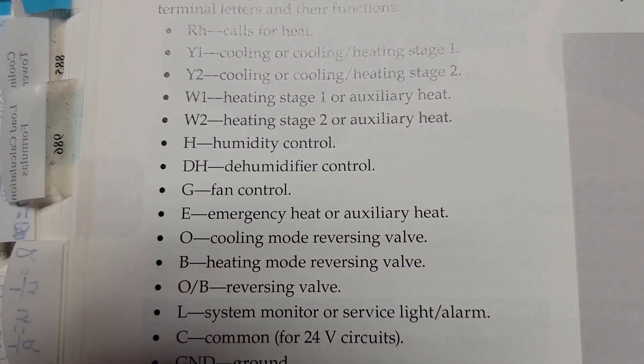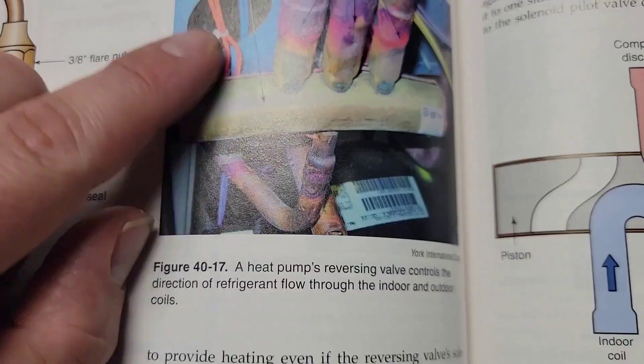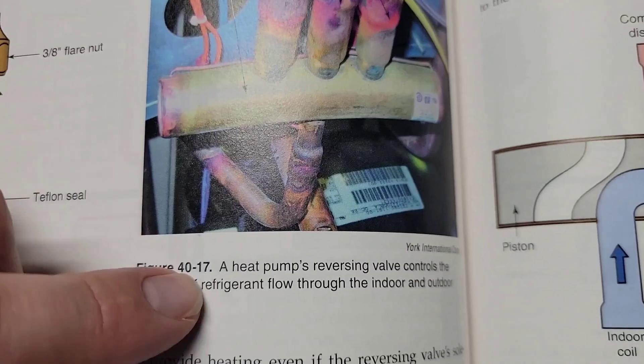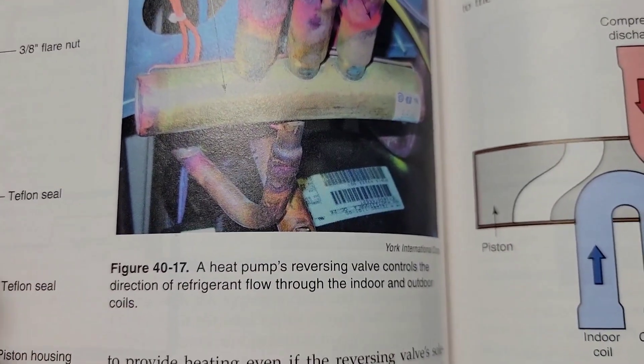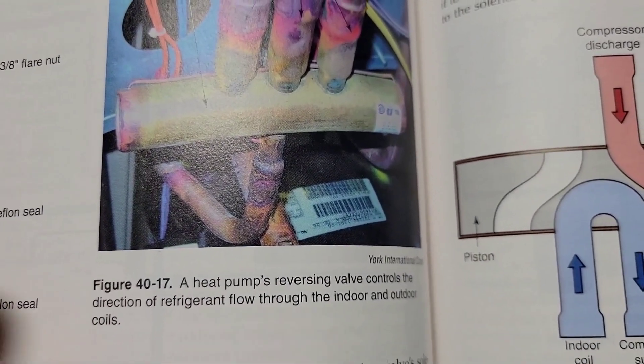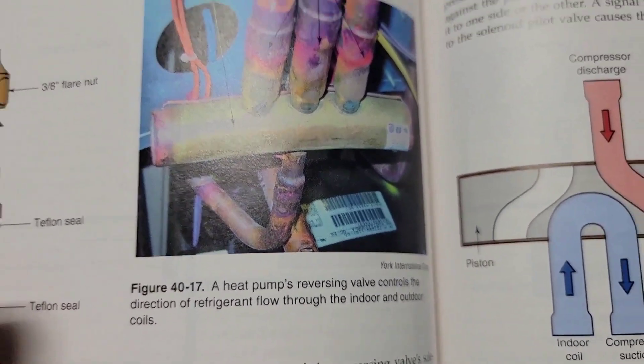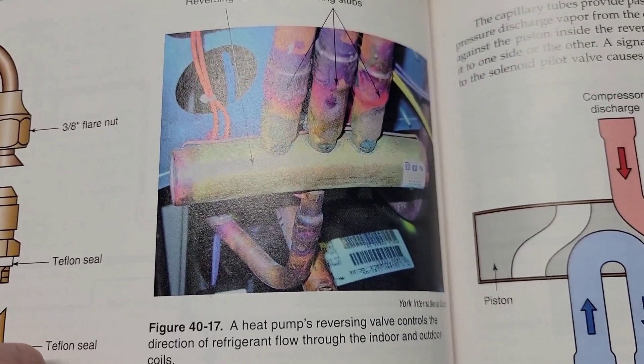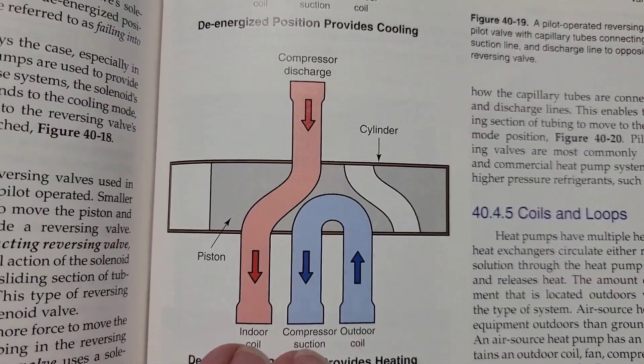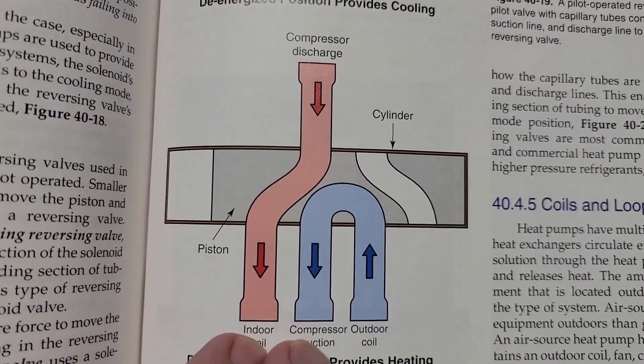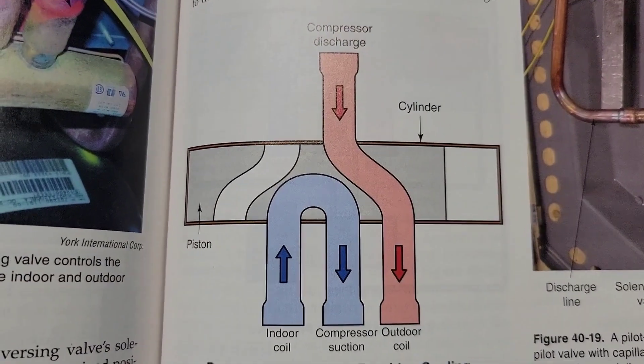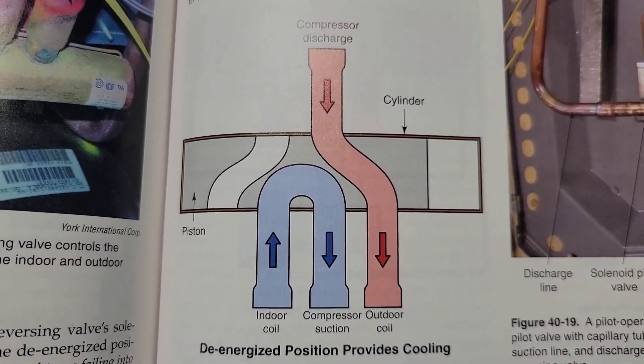Or energizing in heating. For this particular unit, it was B and it was energizing in heating. Here is a picture of the reversing valve. A heat pump's reversing valve controls the direction of refrigerant flow through the indoor and the outdoor coils.